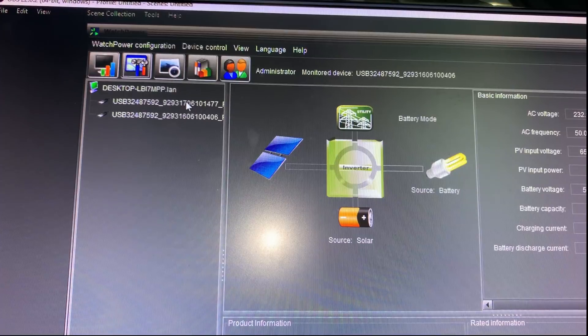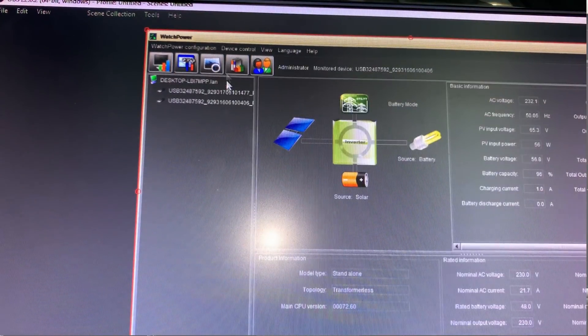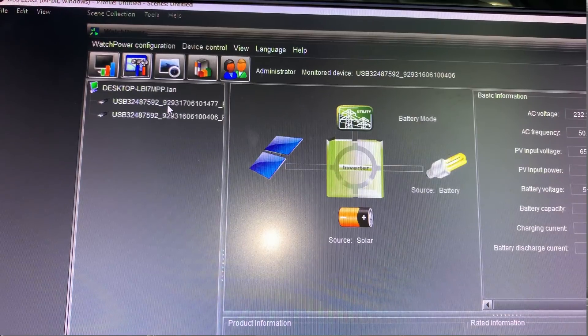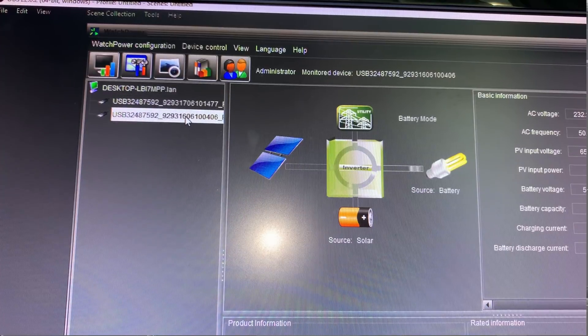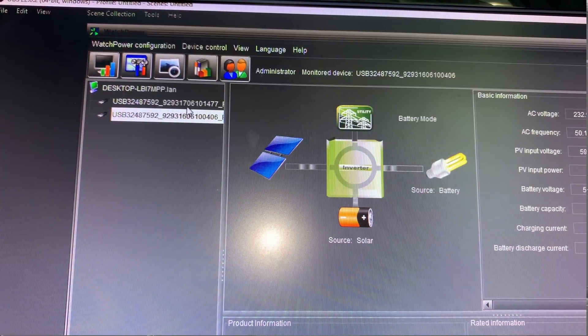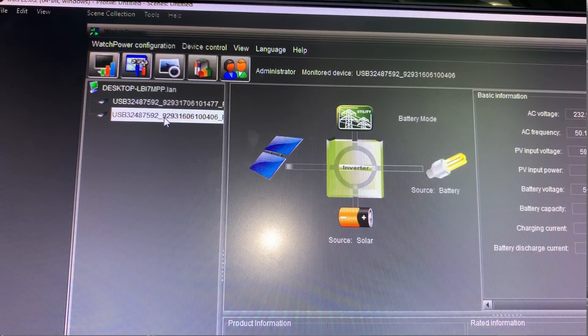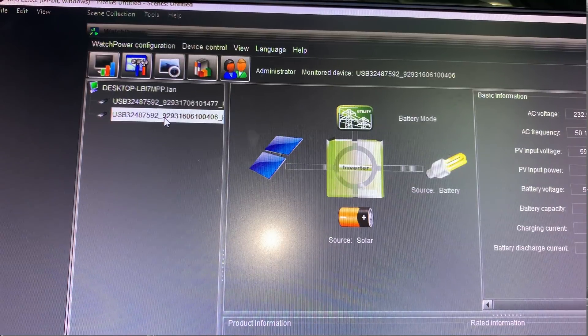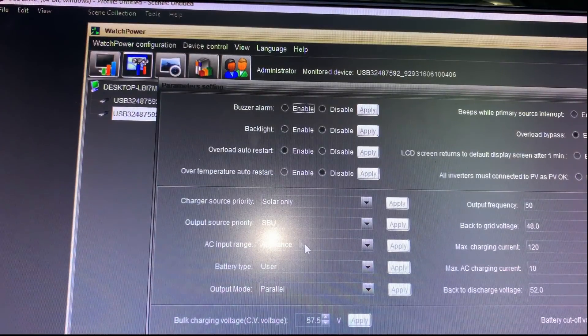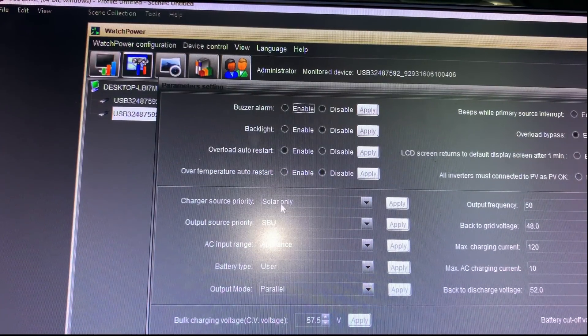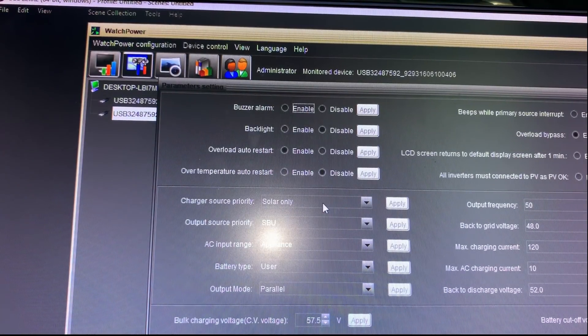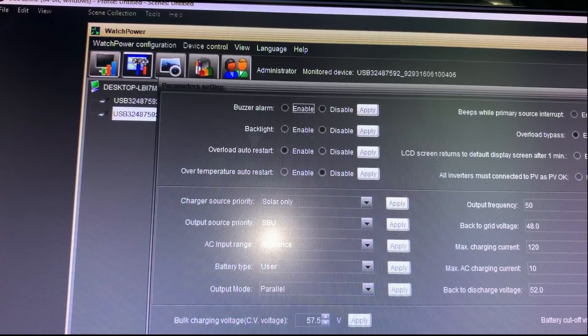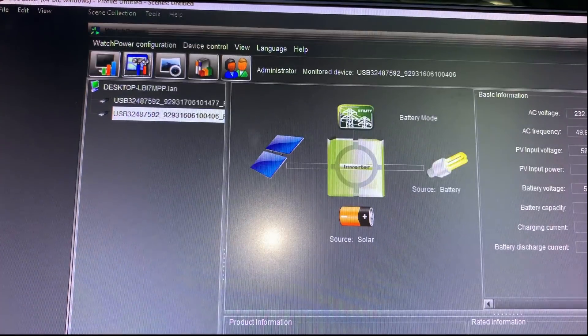Now this battery cutoff here is 47 volts. Now that's important—that one overrides this one here, this back to grid voltage, but only when there is no grid. If there is grid it looks at this one. If there's no grid it looks at this one. So that's an important distinguishment between the two. So there we go—they're the both inverters. Now with this software you have to manually change—you've got to click on each one of these to each inverter to change the state of charge. So if I want to do one and not the other with solar or even grid charging, you have to double click on that and then click that there to actually select that inverter.